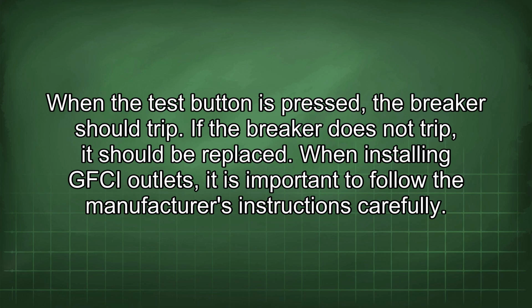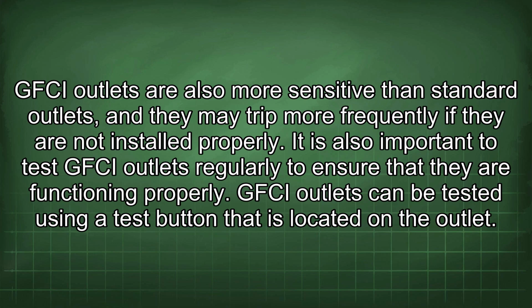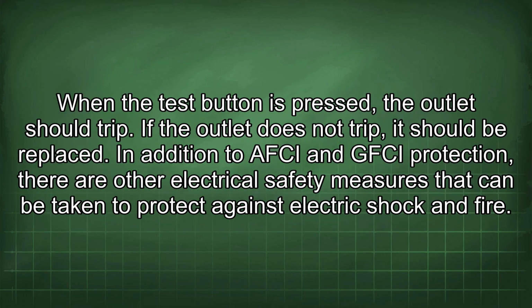When installing GFCI outlets, it is important to follow the manufacturer's instructions carefully. GFCI outlets are also more sensitive than standard outlets, and they may trip more frequently if they are not installed properly. It is also important to test GFCI outlets regularly to ensure that they are functioning properly. GFCI outlets can be tested using a test button that is located on the outlet. When the test button is pressed, the outlet should trip.